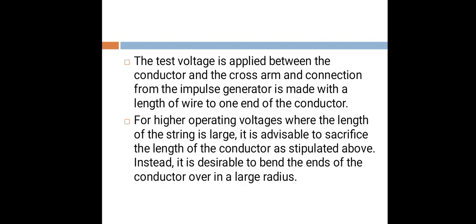For higher operating voltages where the length of the string is large, it is advisable to sacrifice the length of the conductor as stipulated above. Instead, it is desirable to bend the end of the conductor over in a large radius.